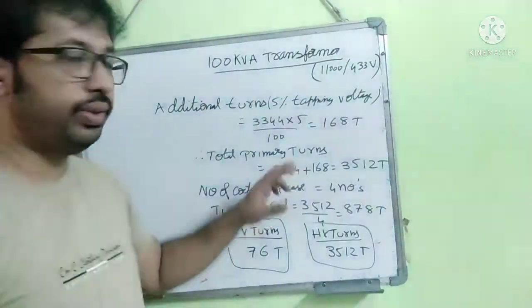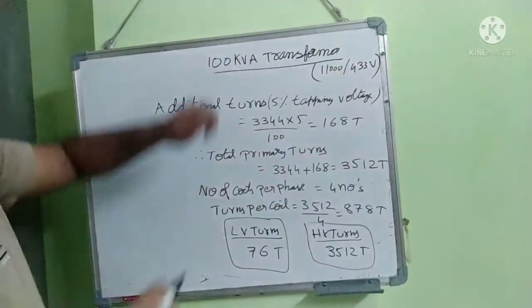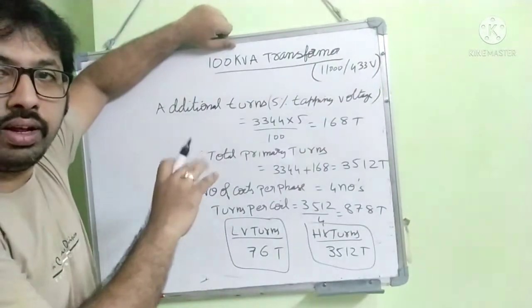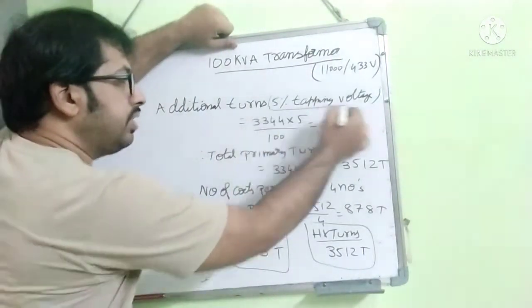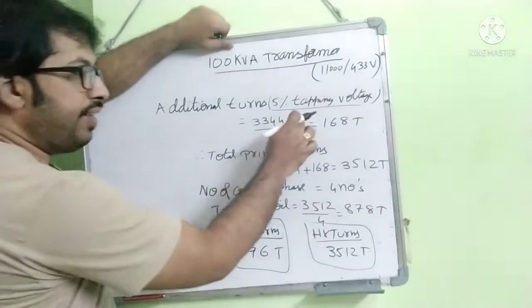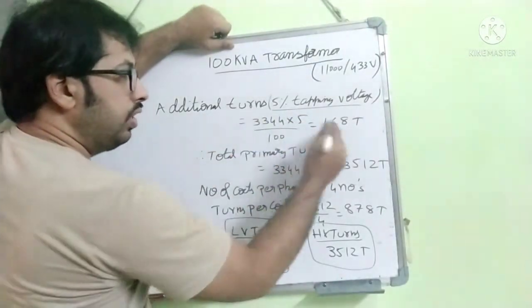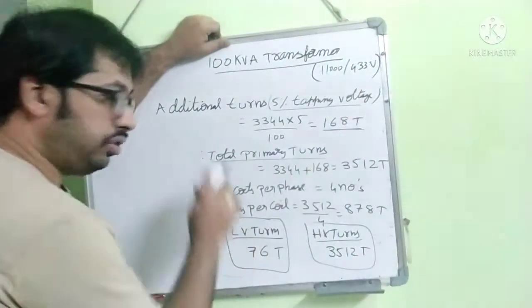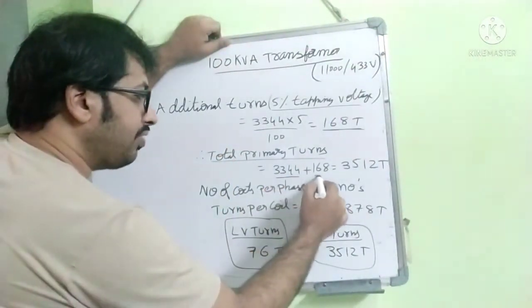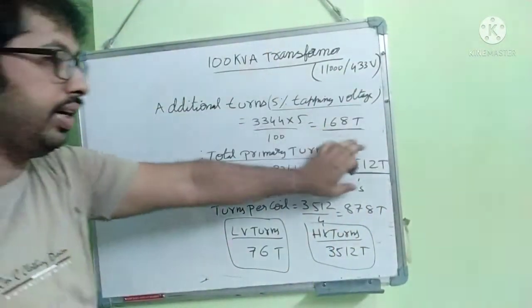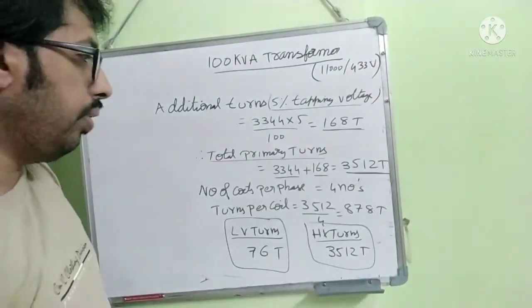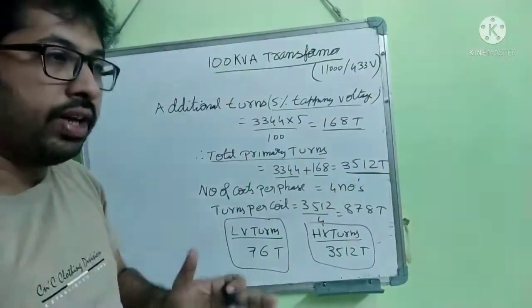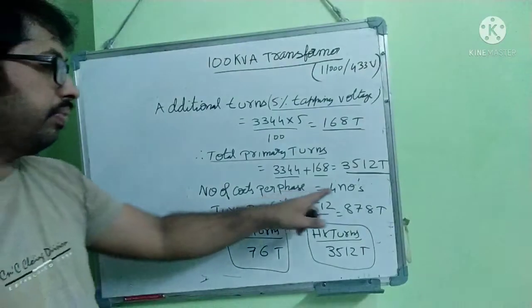Now we will calculate the additional turns which is 5% tapping voltage. This is given in specifications. What are the turns we got? 3344 turns, total turns without tapping voltage. So for that, since we have given 5% tapping voltage, into 5 by 100. So total extra turns we have to place for tappings is 168 more turns. So total number of turns, primary coil turns, HV winding primary, 3344 plus 168 turns, 3512 turns, total HV winding turns.